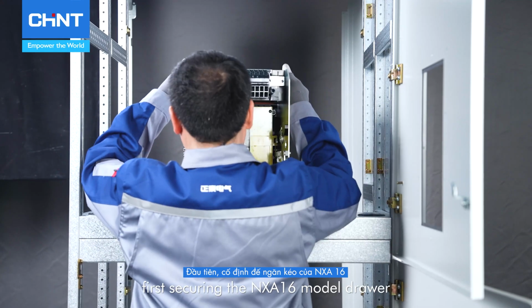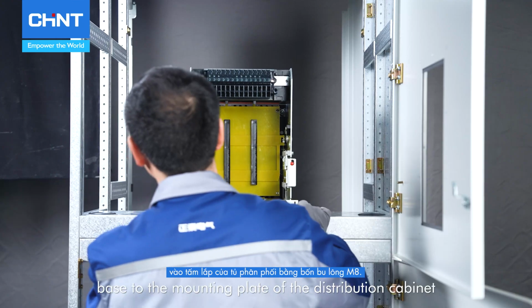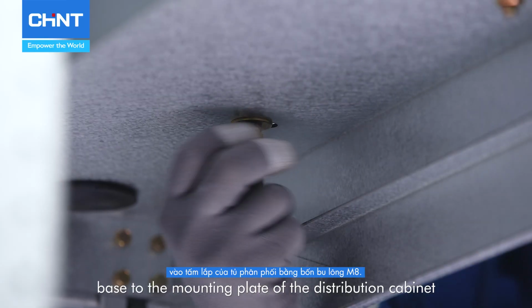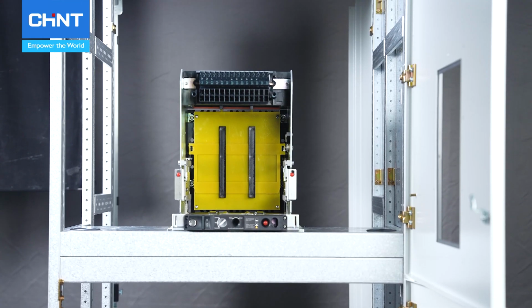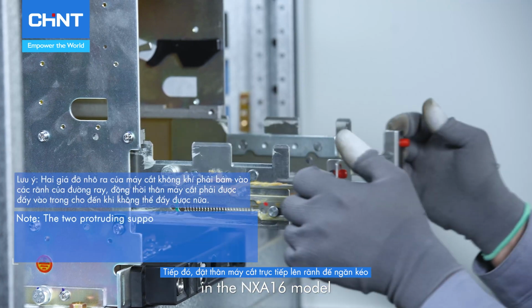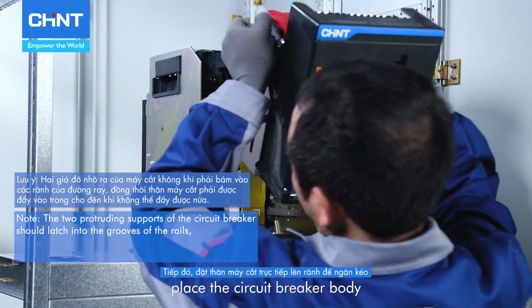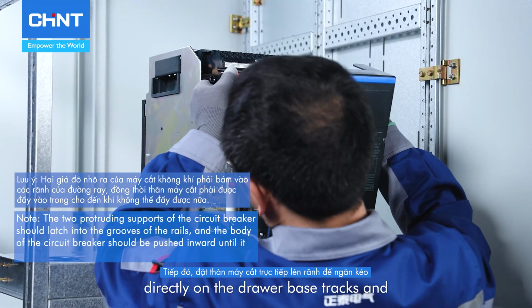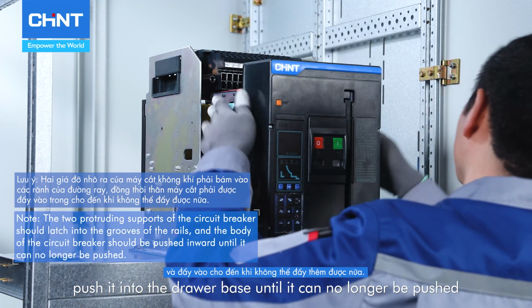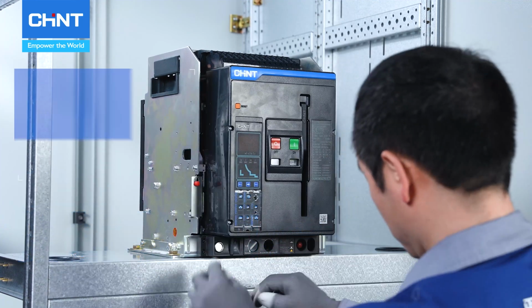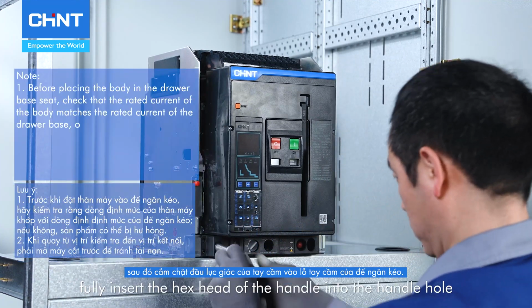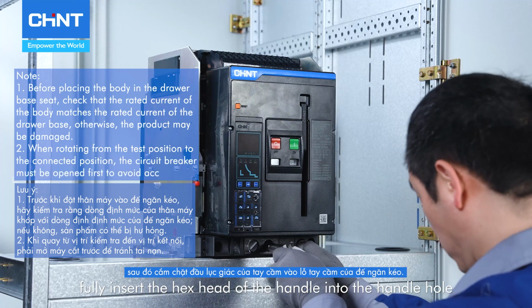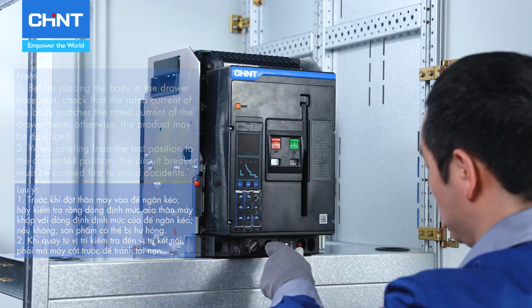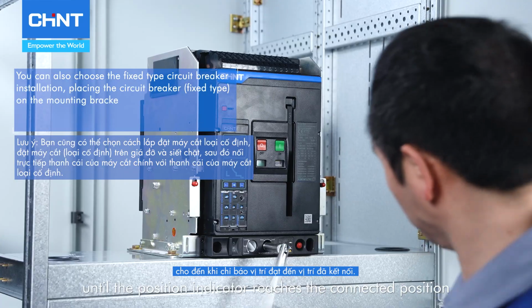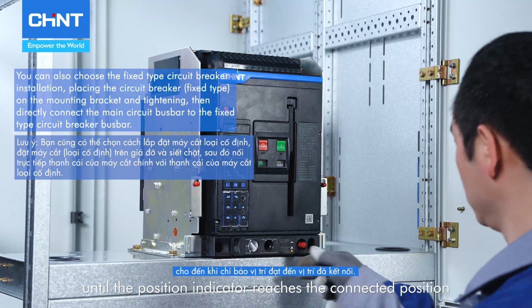First, secure the NXA 16 model drawer base to the mounting plate of the distribution cabinet with 4 M8 bolts. In the NXA 16 model, place the circuit breaker body directly on the drawer base tracks and push it into the drawer base until it can no longer be pushed. Extract the handle, fully insert the hex head of the handle into the handle hole of the drawer base seat. Rotate the handle clockwise until the position indicator reaches the connected position.